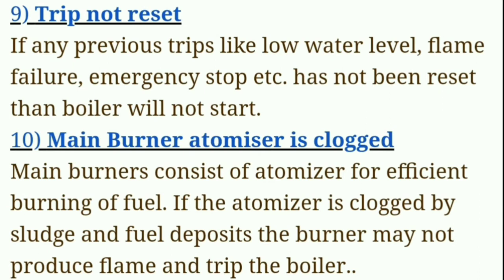Ninth, trips not reset. If any previous trips such as low water level, flame failure, or emergency stop have not been reset, the boiler will not start. Tenth, the main burner atomizer is clogged. Main burners consist of an atomizer for efficient burning of fuel. If the atomizer is clogged by sludge and fuel deposits, the burner may not produce a flame and will trip the boiler.